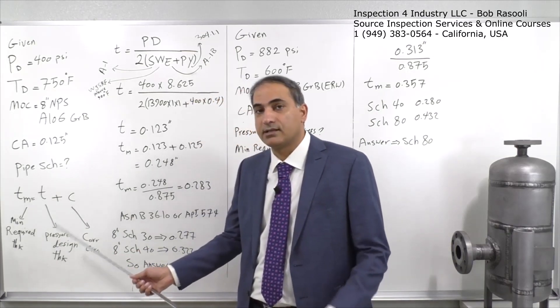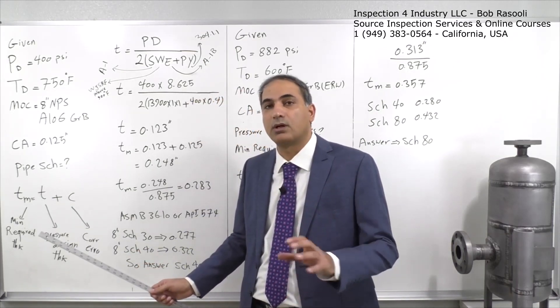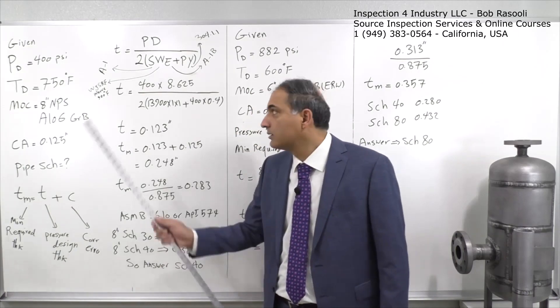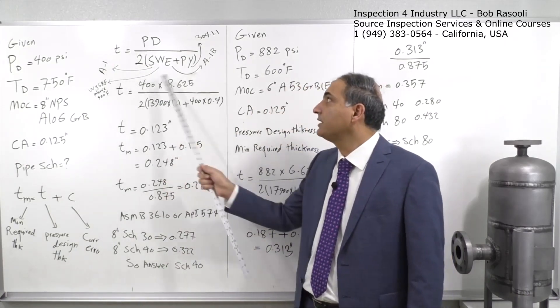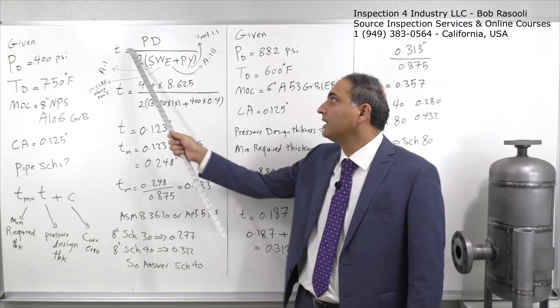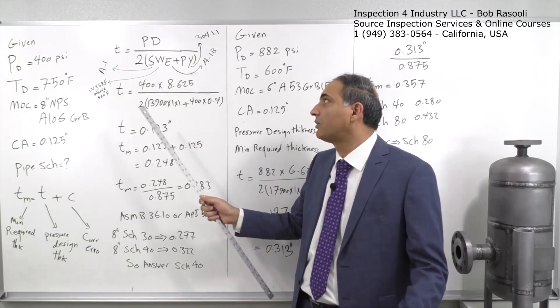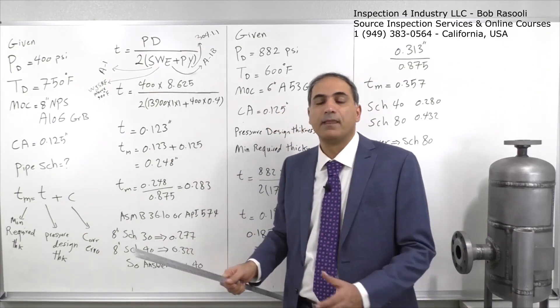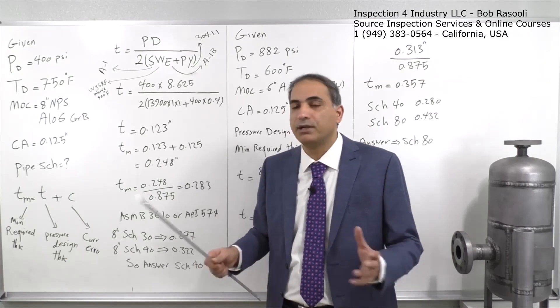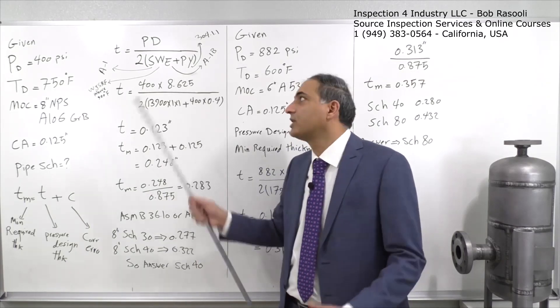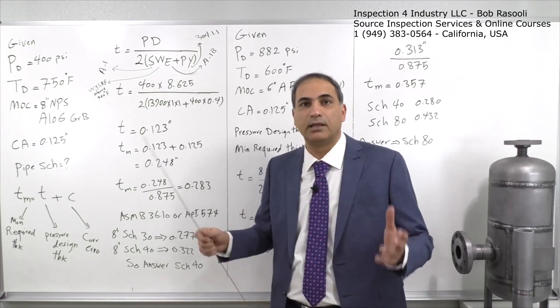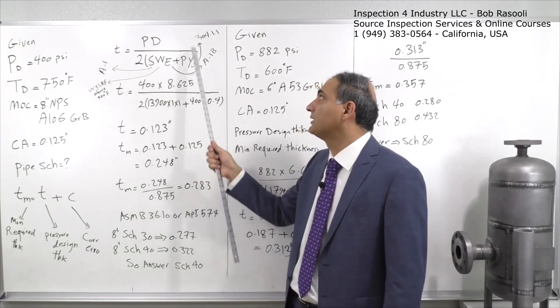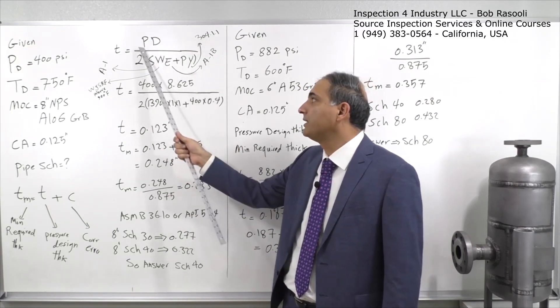The pressure design thickness is the wall thickness needed to overcome internal static pressure, plus the corrosion allowance. I've written the formula from Section 304.1.1 — it is the Barlow formula, modified with safety factors. Similar formulas exist for pressure vessels and pipelines, each adding or removing certain terms. In this modified version, P is the design pressure.